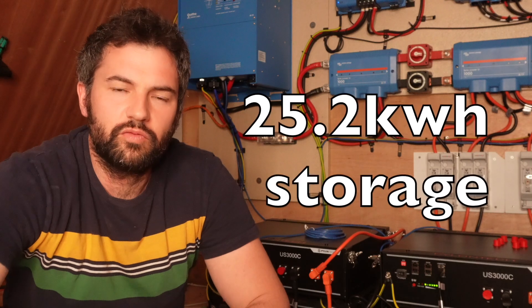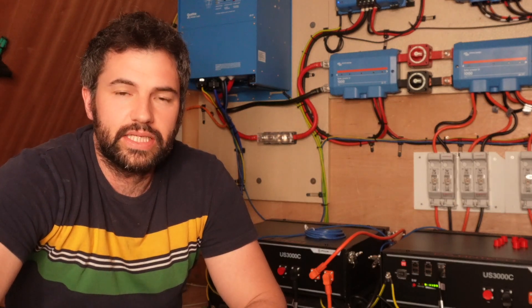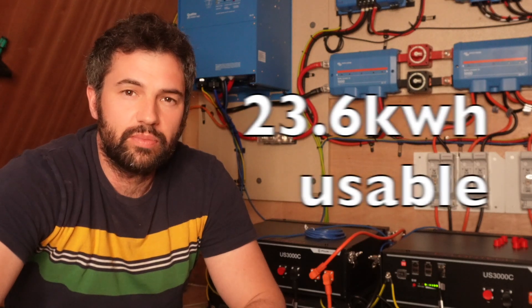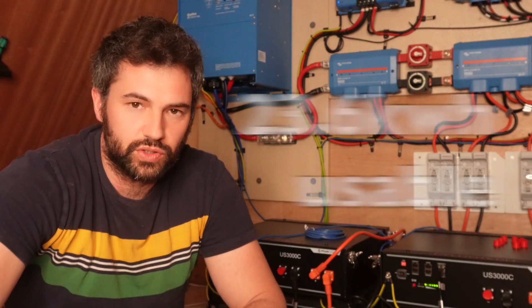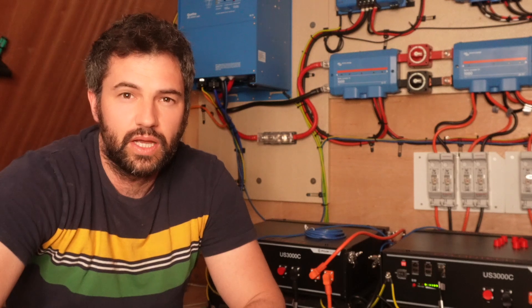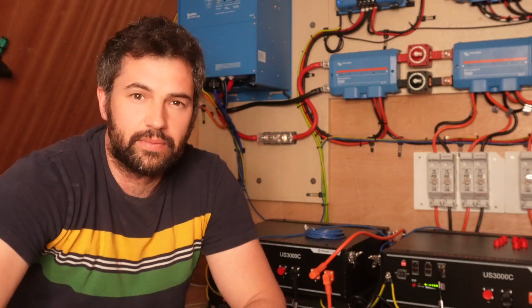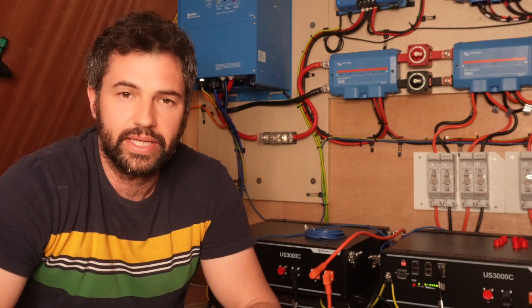We have 25.2 kilowatt hours of storage in these batteries, but we only have 23.6 of usable storage because these go down to 95% depth of discharge. This video is really about how we're getting on with our Pylontech and Victron gear.